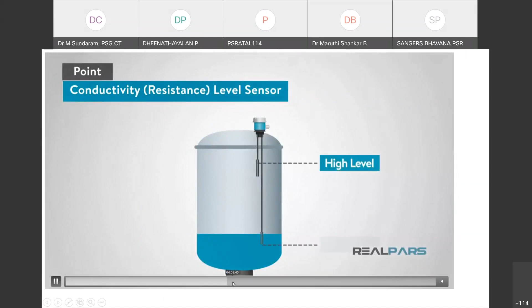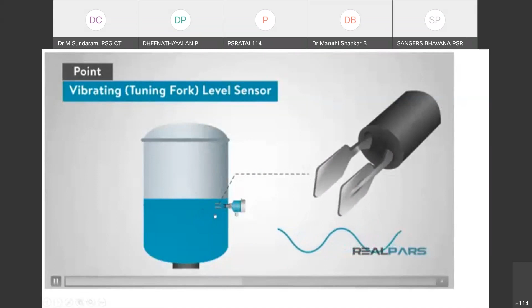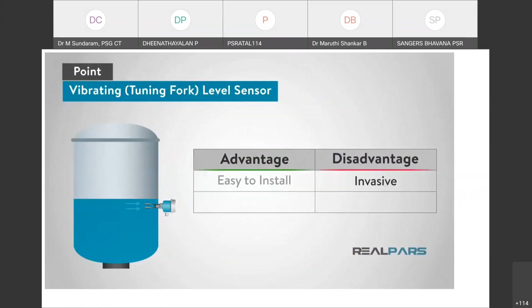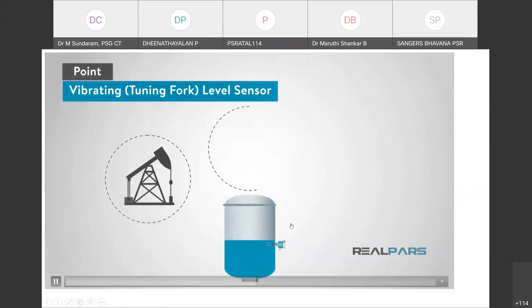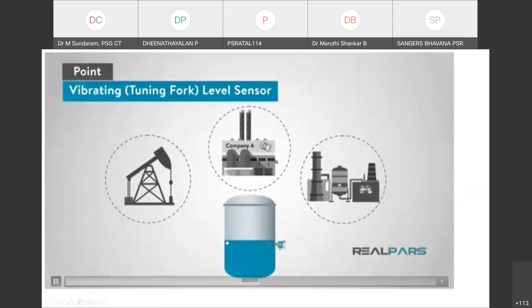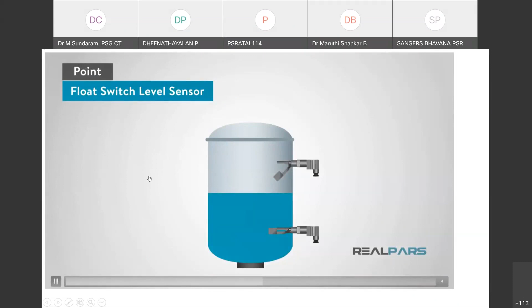This is another interesting one. It's a tuning fork. It is a kind of vibration sensor. A special alloy is made so that whenever the liquid changes the medium, it will start to vibrate. That vibration frequency will be used for detecting the level. Again, it has some issues in the fine-tuning calibration. So in a few applications, wherever the quantity keeps on changing, then only you will get some vibration. Those are the places where it is being used.